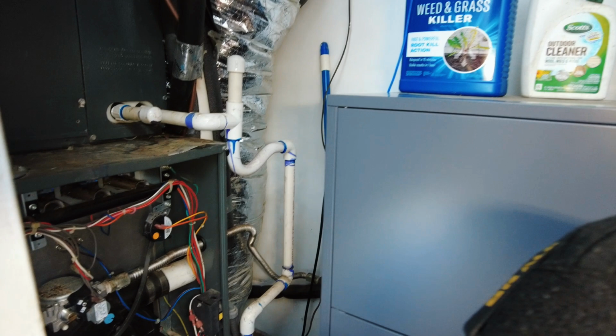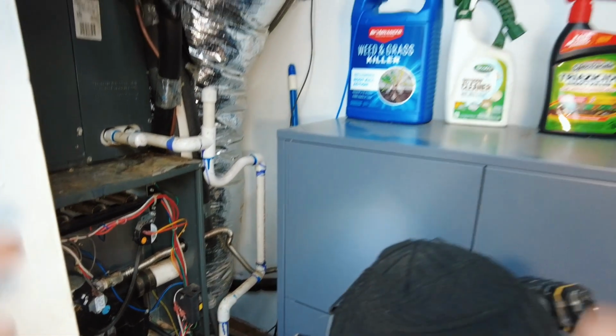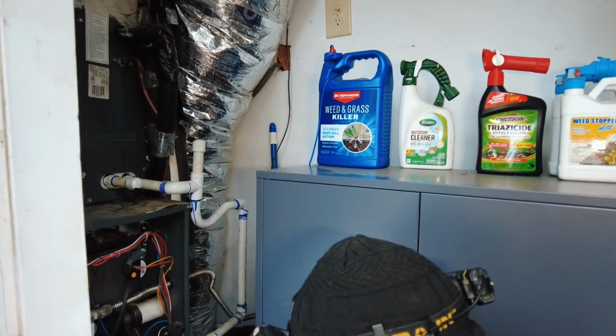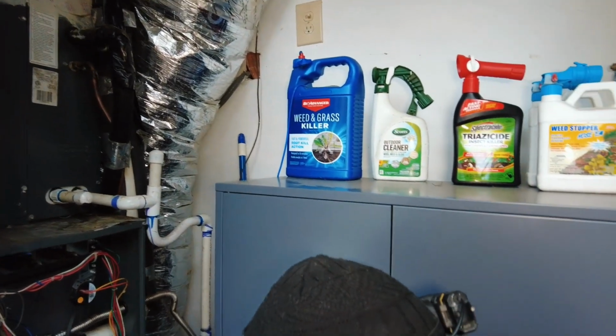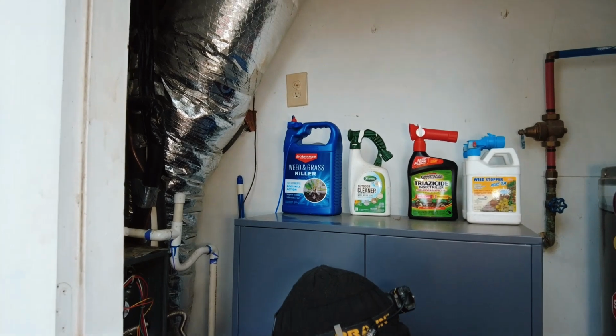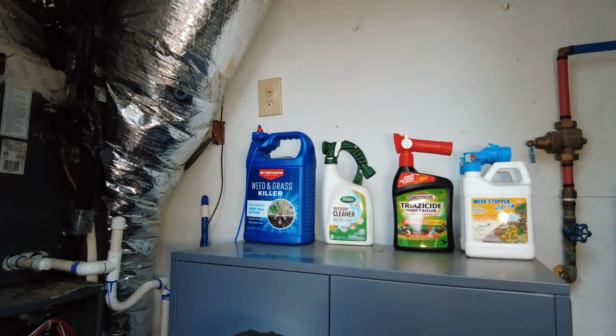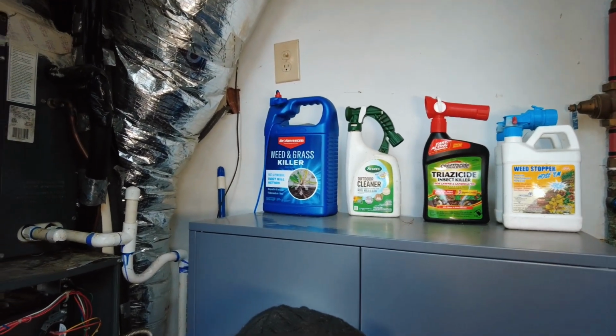There was just so much to mention with this install, but I didn't want to shotgun a bunch of issues at the customer and overwhelm them, so I was telling them little by little. But there's no plenum connected to it, and that's another reason why your static pressure is higher than it should be, and why your airflow is probably going to be a bit worse than it should be.